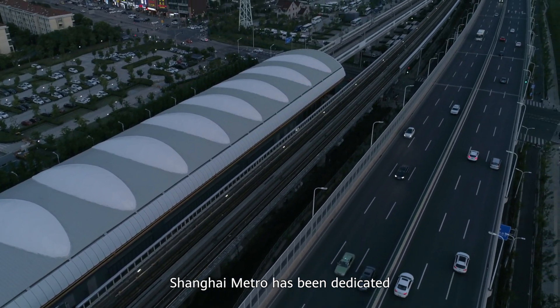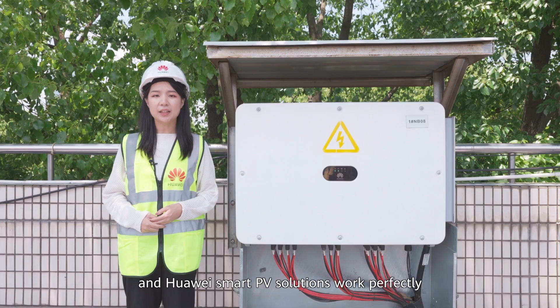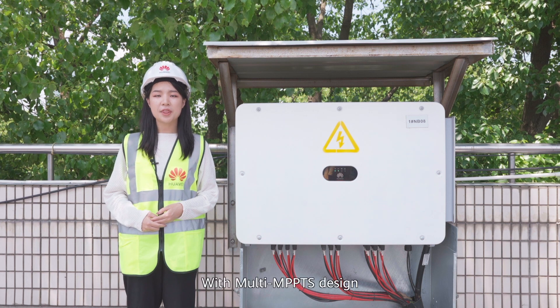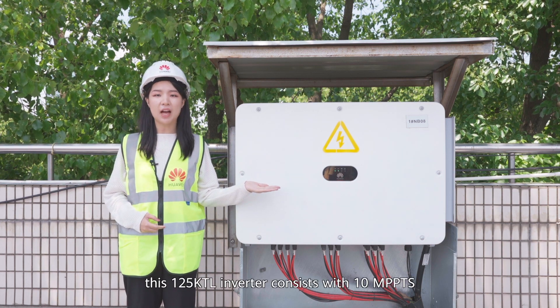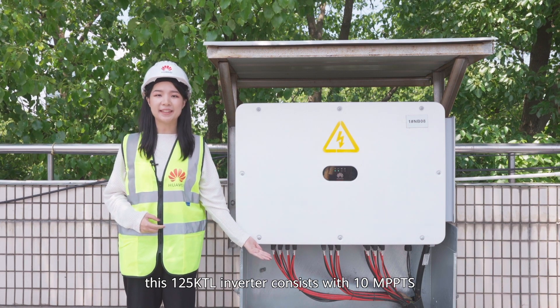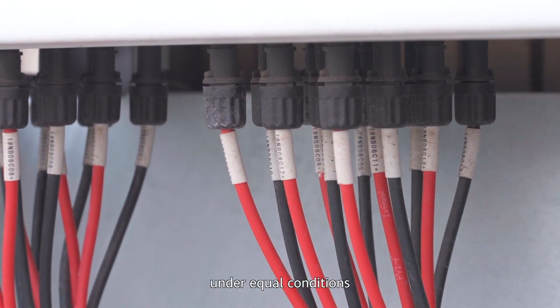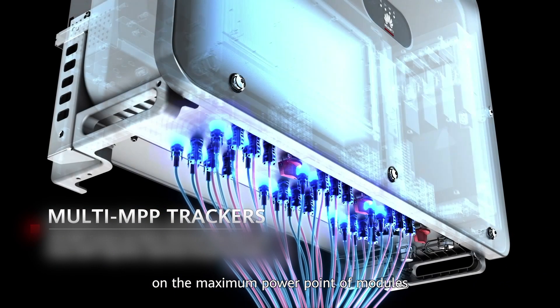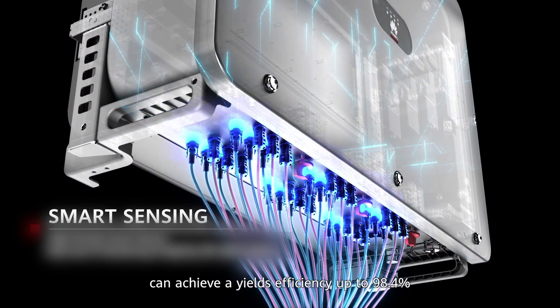Shanghai Metro has been dedicated to the construction of smart green solutions for years, and Huawei Smart PV solutions work perfectly with its ambitions. With multi-MPPT designs, these 125KTL inverters consist of 10 MPPTs. According to the barrel effect, under equal conditions, the more MPPTs you have, the fewer strings per MPPT connect. Therefore, the tracking of the maximum power point of modules can achieve yield efficiency up to 98.4%.